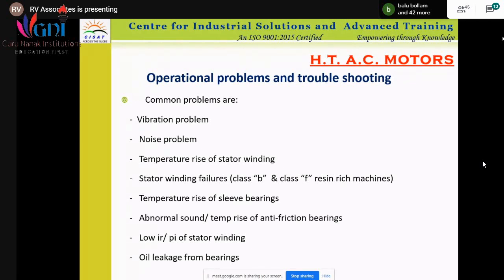These are the common problems: vibration, noise, temperature rise, stator winding failure, temperature rise of bearings. There are two bearings, a driving end bearing and a non-driving end bearing. Both bearings can fail because of these abnormal conditions. Then there may be an oil leakage in the bearing. Like a transformer, which has a tank and oil circulated through a pump around the entire winding for cooling, in the motor the same system is available.